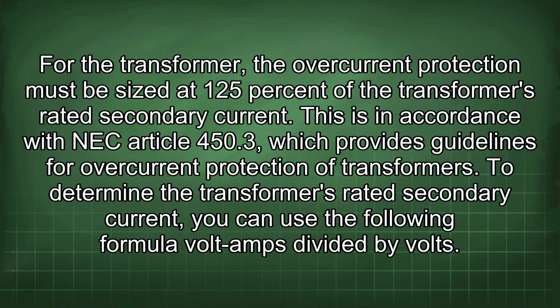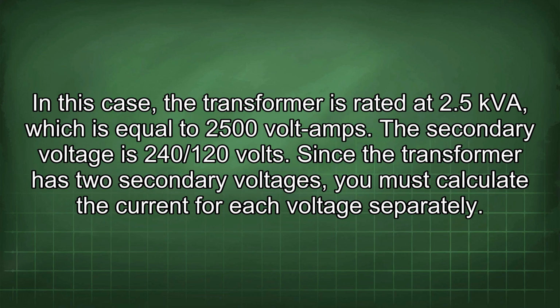For the transformer, the overcurrent protection must be sized at 125% of the transformer's rated secondary current. This is in accordance with NEC Article 450.3, which provides guidelines for overcurrent protection of transformers. To determine the transformer's rated secondary current, you can use the following formula: voltamps divided by volts. In this case, the transformer is rated at 2.5 kVA, which is equal to 2500 voltamps. The secondary voltage is 240/120 volts. Since the transformer has two secondary voltages, you must calculate the current for each voltage separately.